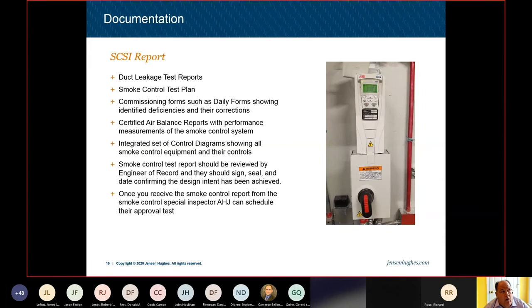So, as you're all aware, fire and life safety systems are some of the last systems to get tested and accepted when opening a new building. Smoke control is on that list of one of the last ones that gets done, because a lot of times you're even having your fire alarm signed off before the smoke control system is fully signed off.